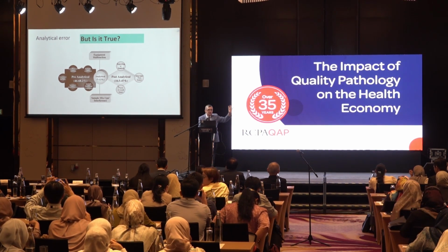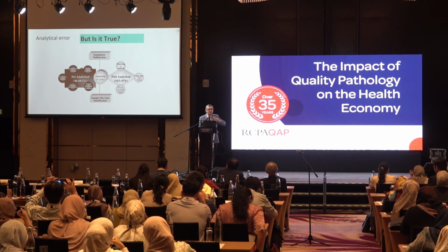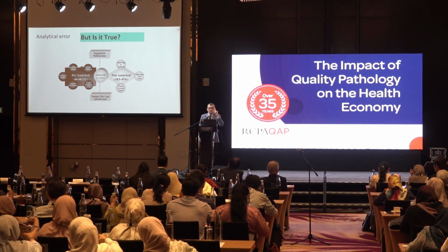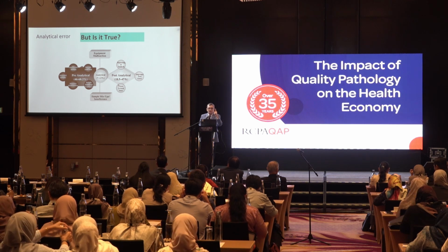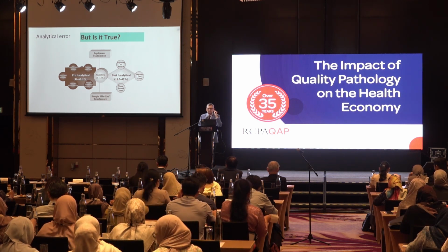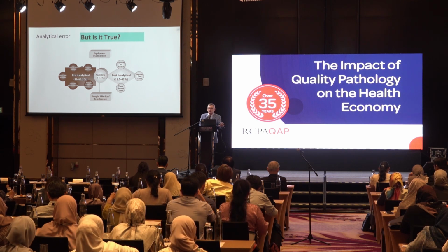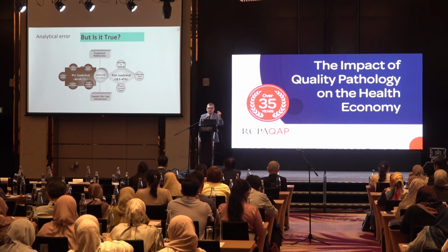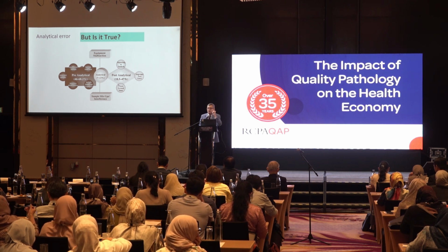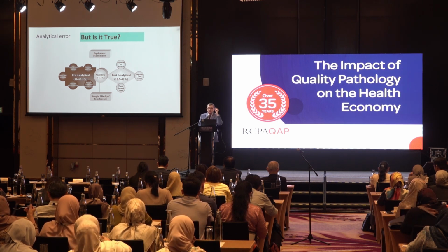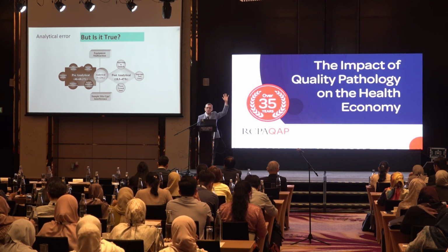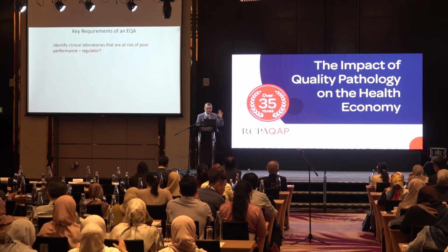Okay, I know we can't control them, and we've always relied on the manufacturer producing really great analyzers and all that sort of stuff, but we also rely on them producing really high-quality calibration material. Right? We rely on the analyzer being good, and the calibrator that they give us. And if the calibrator value is 123, we assume that that's correct. The manufacturer said it was 123, so therefore it's 123. Right? Wrong.